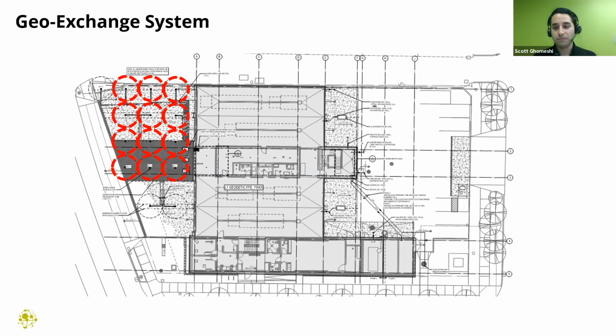Being a very tight site, we talked to the city, and since we had a bit more room to play with, we allowed for an additional 3 boreholes for a couple of reasons. First, to mitigate constructability risk on such a tight site, so if we hit a boulder while digging about 300 feet down, we'd have room to make up for an additional borehole. That gave us the flexibility to do so.